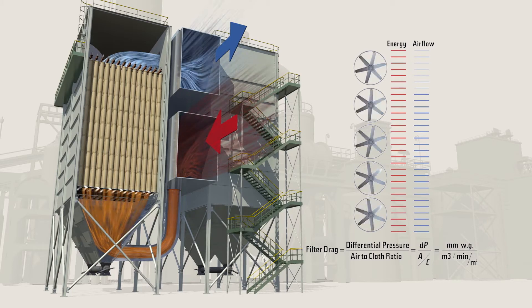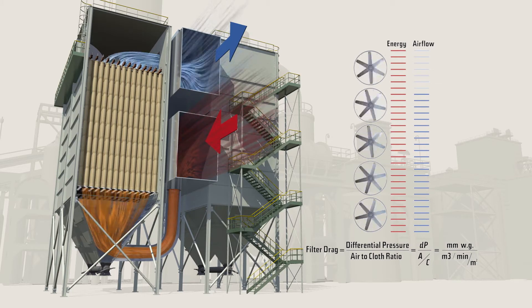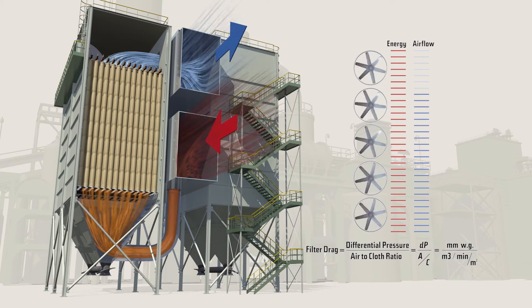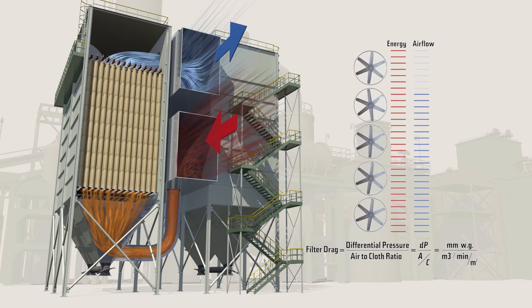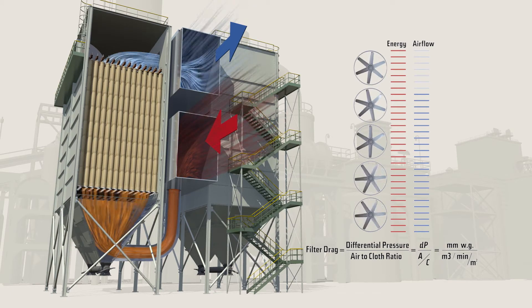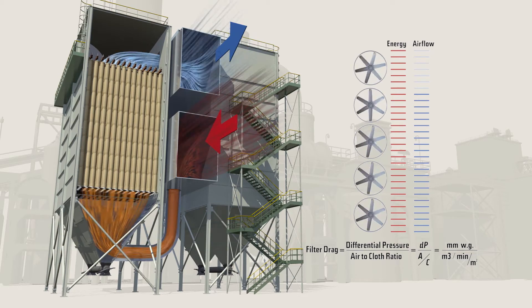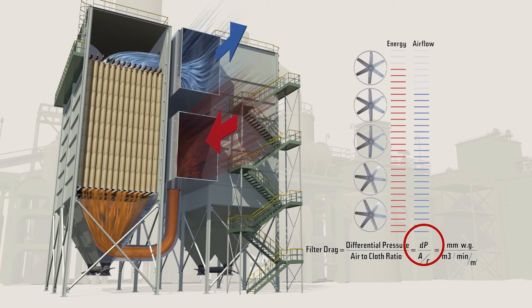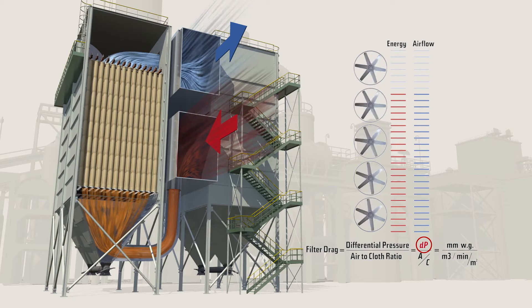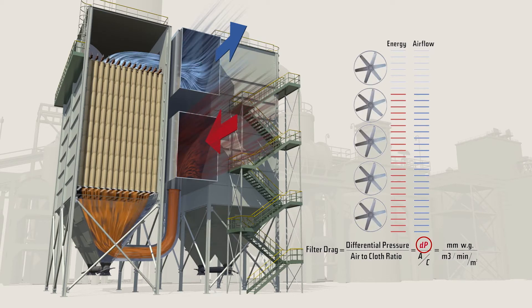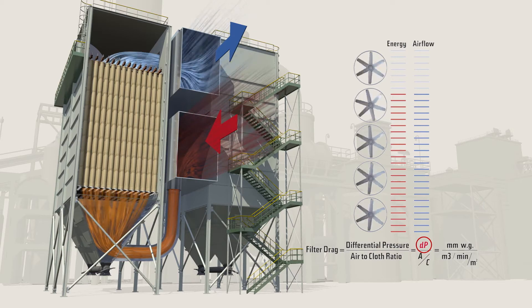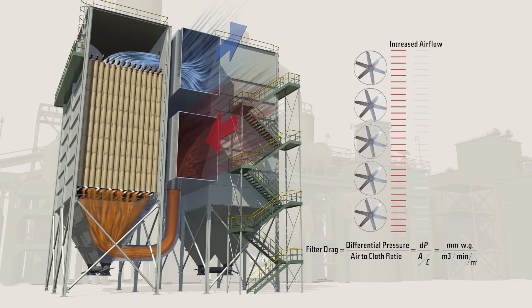Many bag houses on coal-fired boilers are equipped with variable frequency drives on their main ID fan motors. Using Gore Low Drag filter bags will allow for the designed airflow while operating at a 15 to 20 percent lower differential pressure. The fan speed can thus be reduced while maintaining constant flow, using less energy and saving you money.